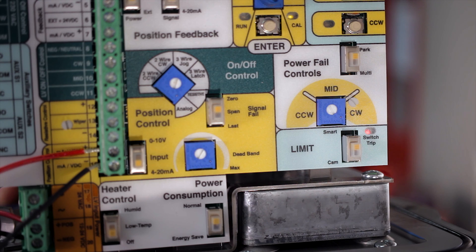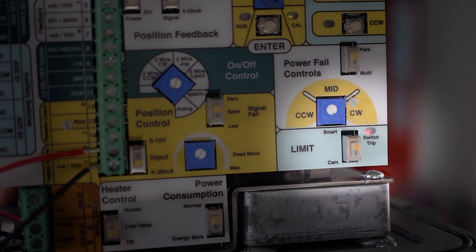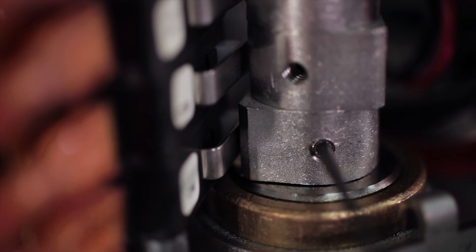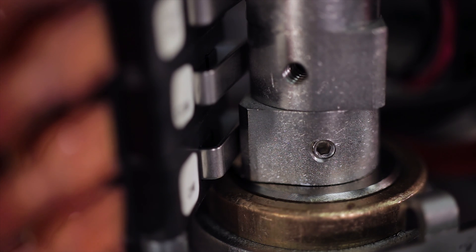If the cams are making contact with the limit switches the switch trip LED light will appear. Loosen the set screw on the cam and retighten in a spot where the valve can have full travel without making contact with the limit switches.